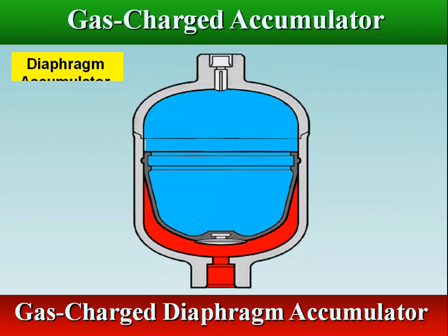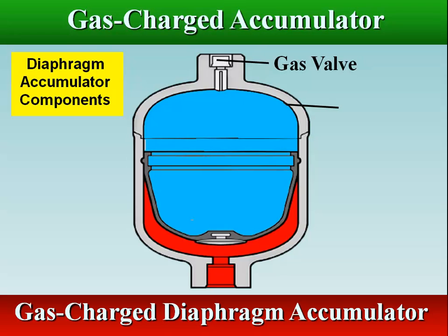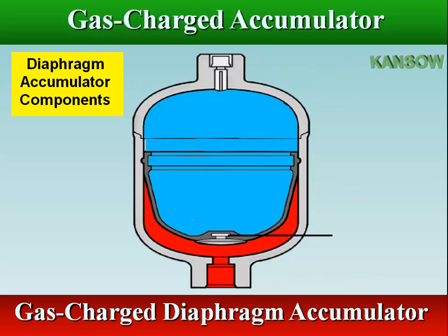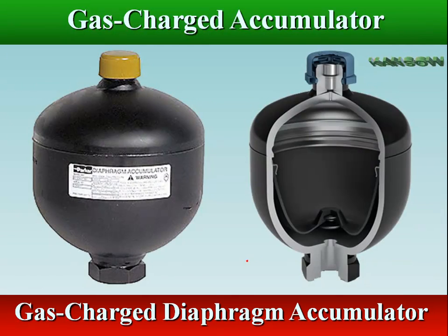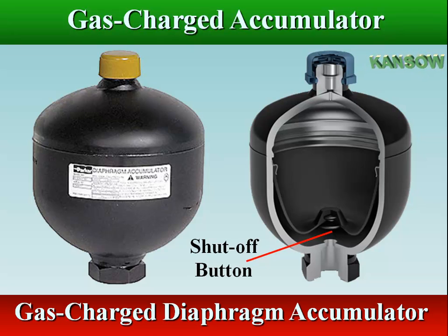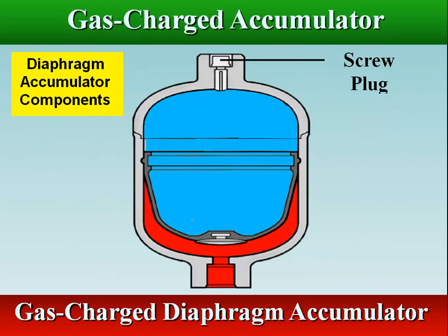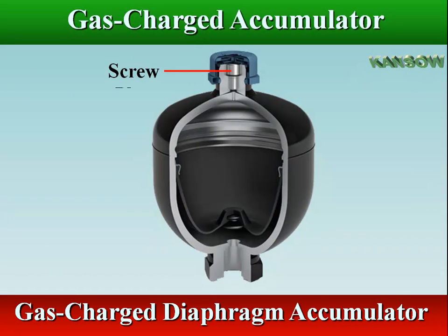Diaphragm type accumulator consists of a diaphragm secured in a shell and serving as an elastic barrier. A shut-off button, secured at the base of the diaphragm, covers the inlet of the fluid connection when the diaphragm is fully stretched. This prevents the diaphragm from being pressed into the opening during the pre-charge period. On the gas side, the screw plug allows control of the charge pressure and the charging of the accumulator by means of a charging and testing device.